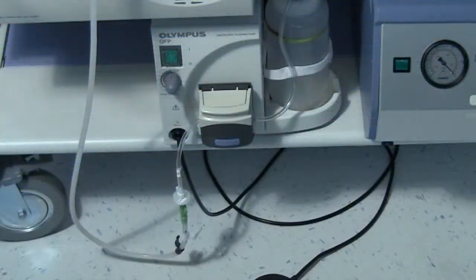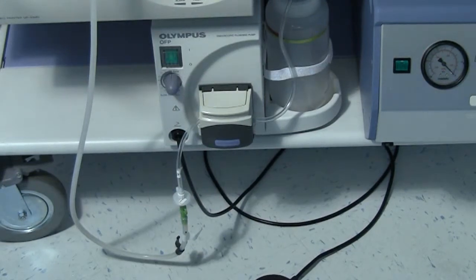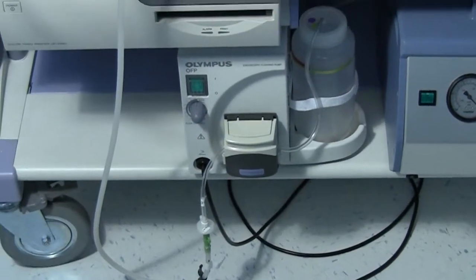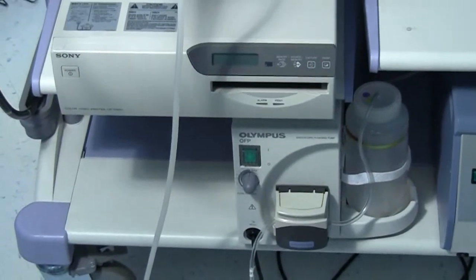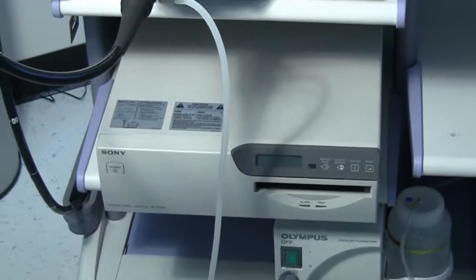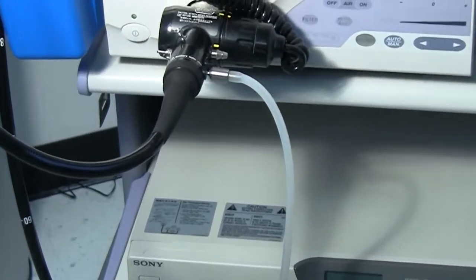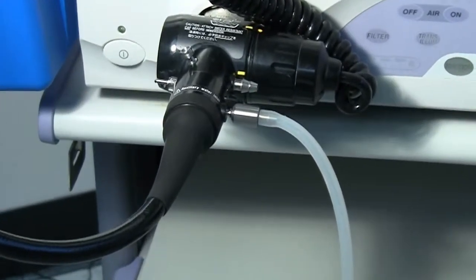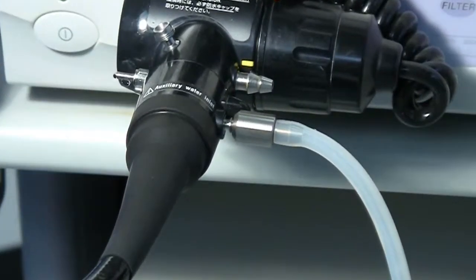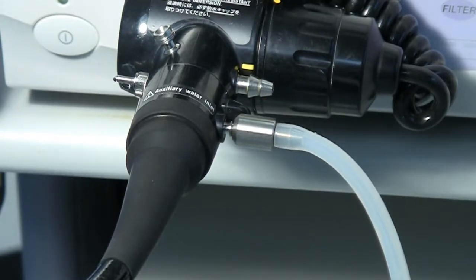In this shot we have an Olympus OFP irrigator with its full tubing setup. It consists of a reusable water bottle, a daily use irrigation tube, a daily use disc filter, and a single-use auxiliary water port connector and tubing. The tubing seen here is connected to the auxiliary water inlet of an Olympus 160 series colonoscope.